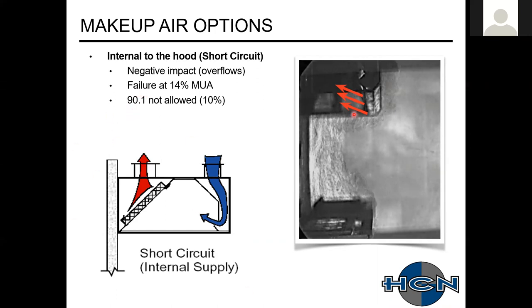Negative impacts. Typically what happens with a lot of this, if you're dumping too much air into this, your spillage is usually towards the back end of the hood and out the sides. You can see some here, but a lot of the spillage and heat is actually towards the back end of the hood because it's interrupting the natural flow of the hood system. And then also, you've made your volume smaller because you're introducing makeup air here, so you're not having as large of a volume for your hood capture.